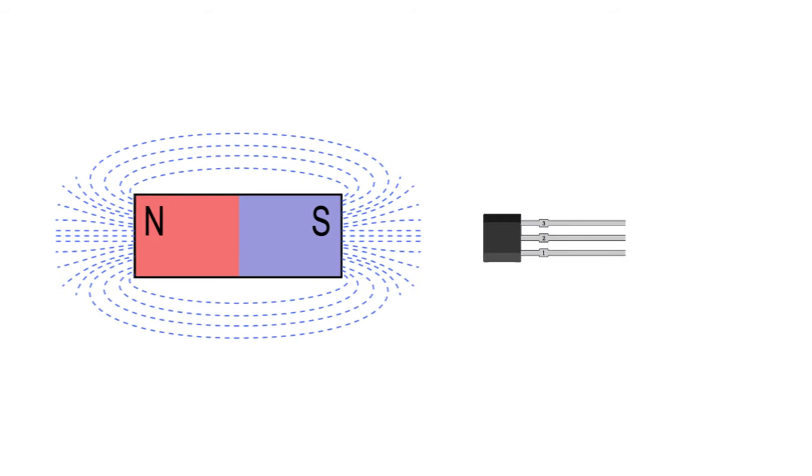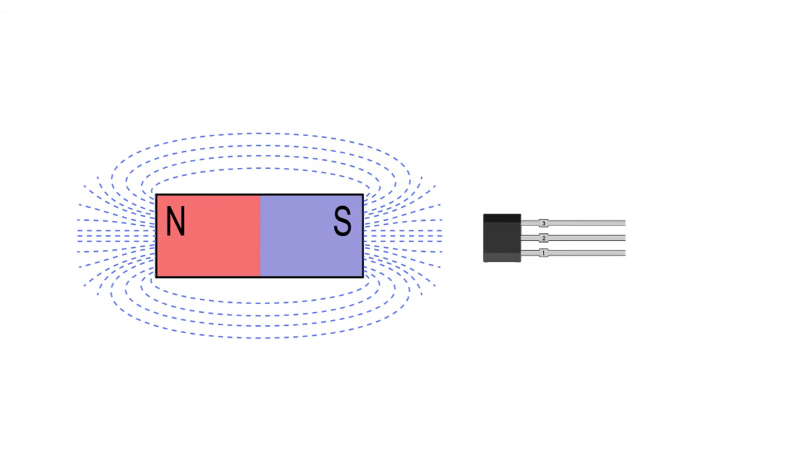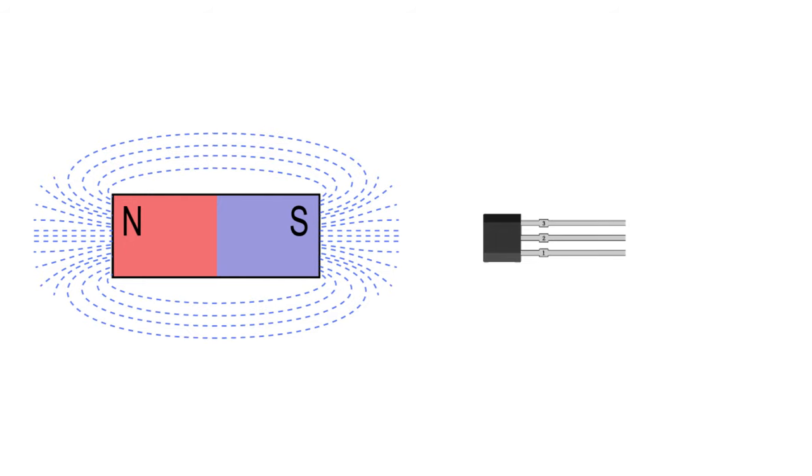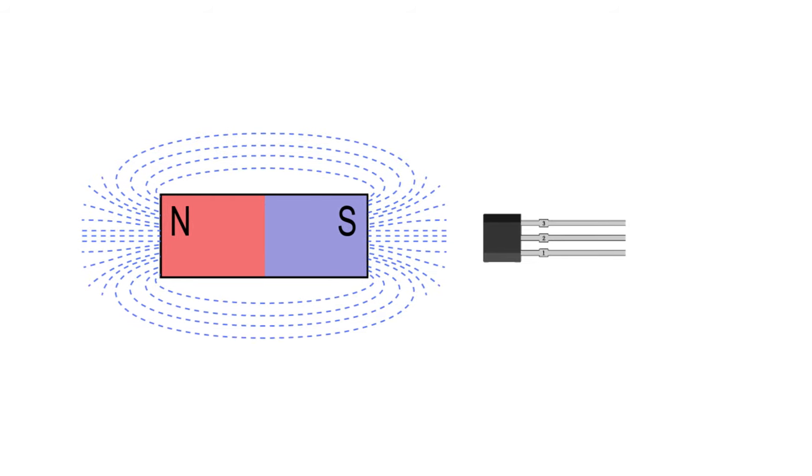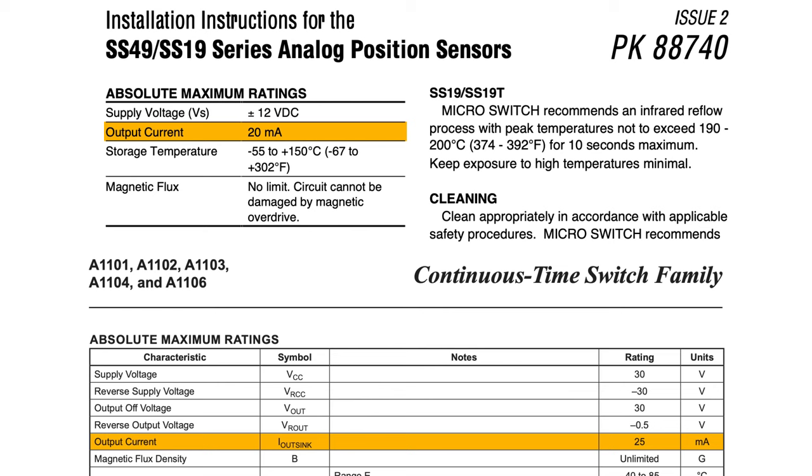To ensure maximum sensitivity, the flux lines should always be perpendicular, with the magnet's pole, where the flux is strongest, pointing at the face of the sensor. The output drive capabilities of Hall effect sensors are very small, so they cannot directly switch large electrical loads.